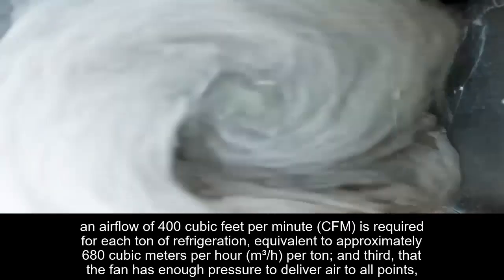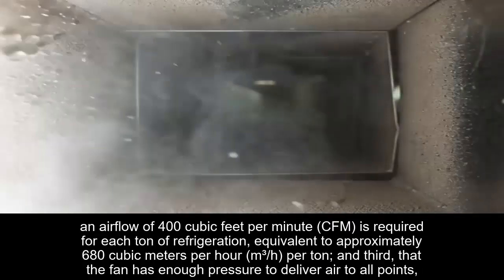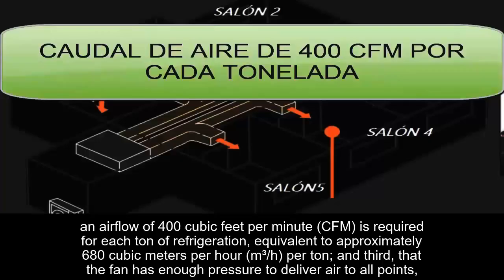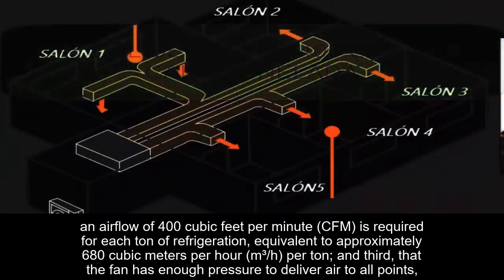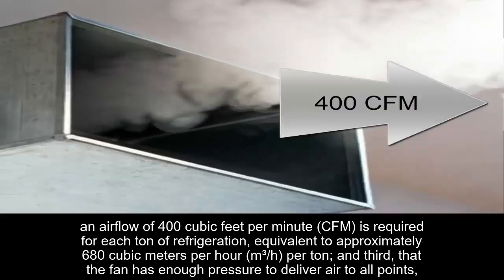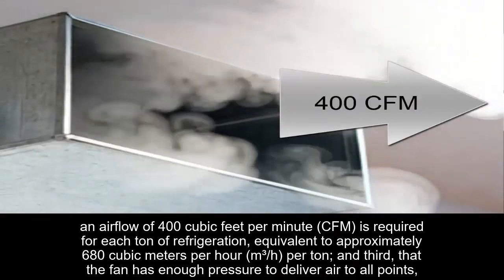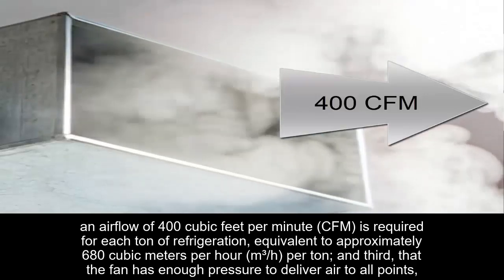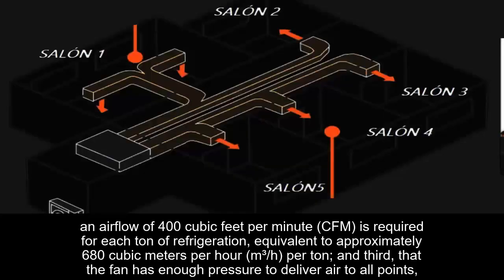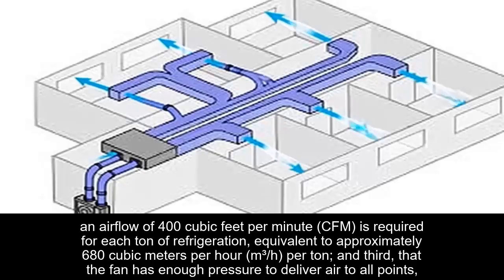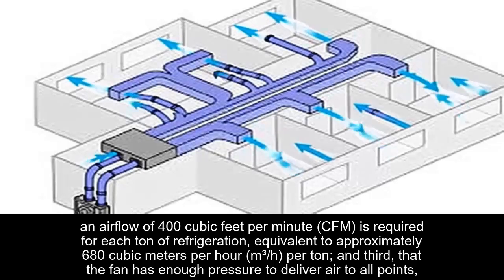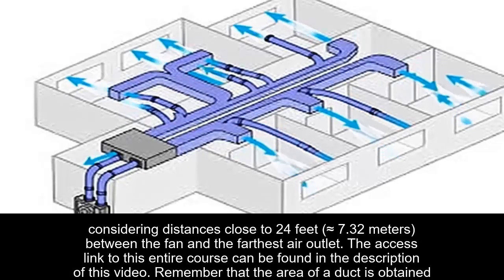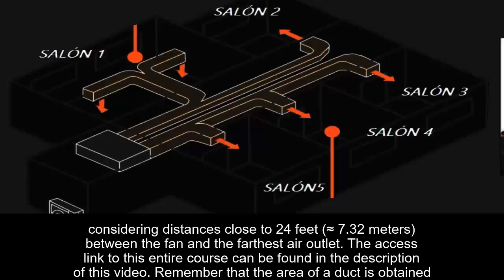Second, remember that an airflow of 400 cubic feet per minute, CFM, is required for each ton of refrigeration, equivalent to approximately 680 cubic meters per hour, m cubed per hour, per ton. And third, that the fan has enough pressure to deliver air to all points, considering distances close to 24 feet, nearly 7.32 meters, between the fan and the farthest air outlet.